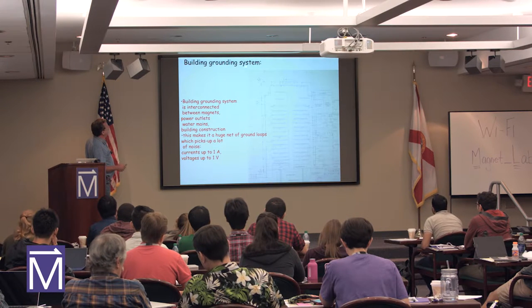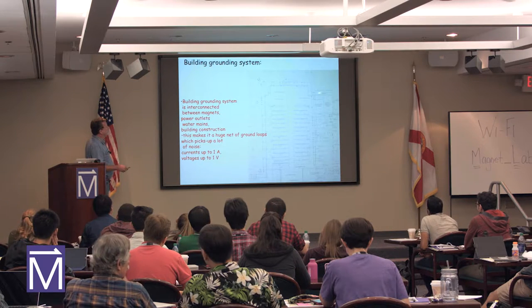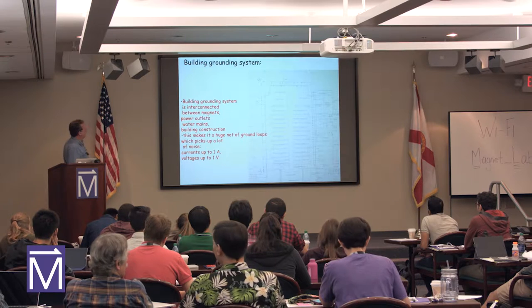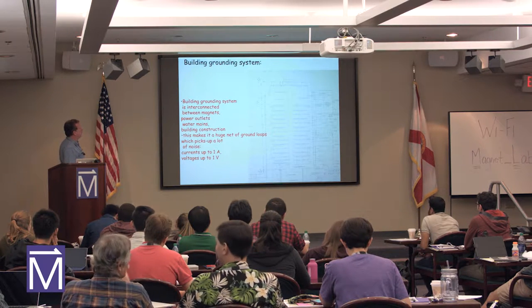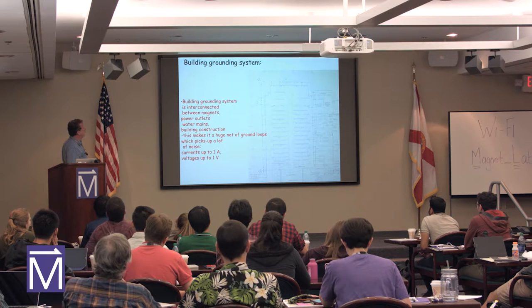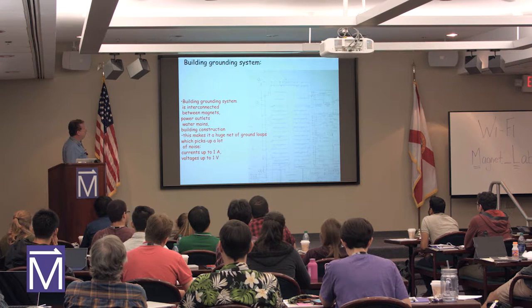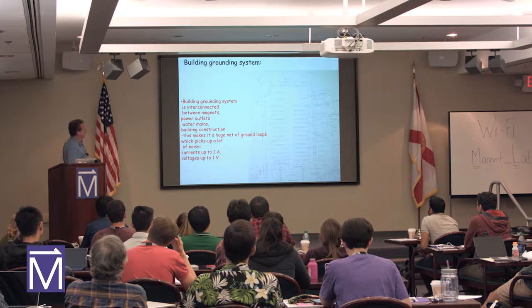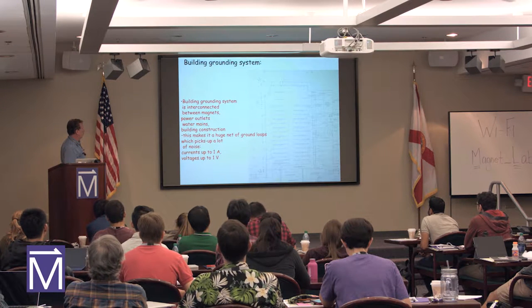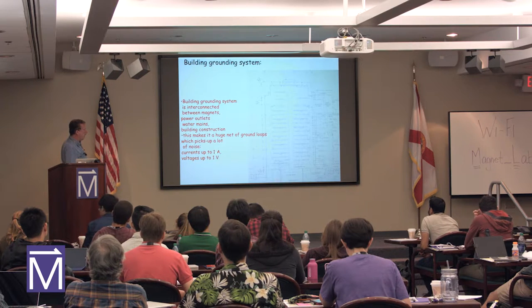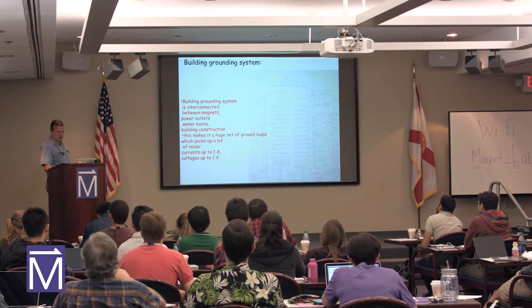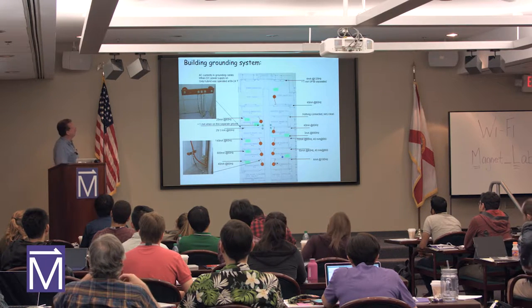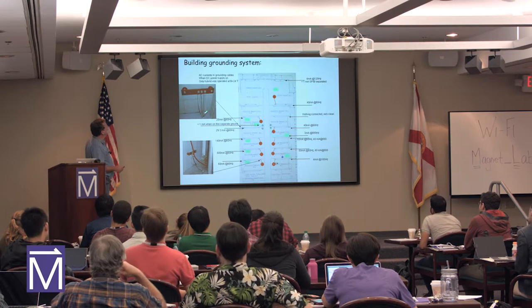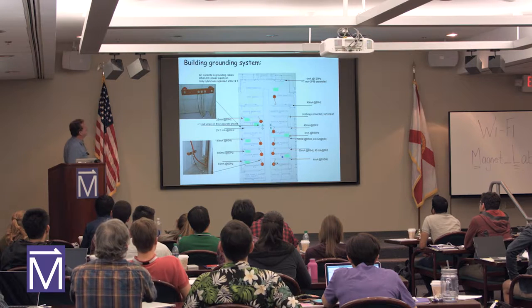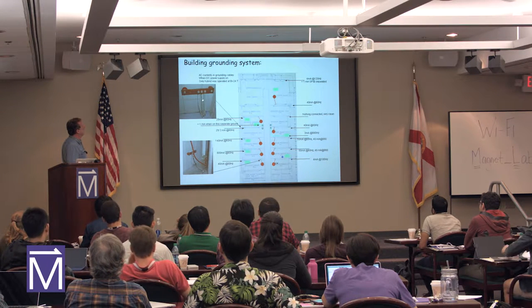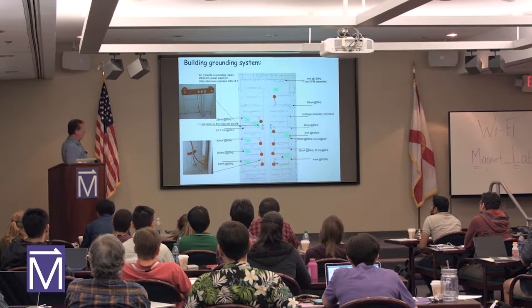Later, we built a new grounding system. This is a blueprint of all the magnets in the DC area. The building grounding system, and this is usually everywhere, is interconnected between magnets, power outlets, water mains, and building construction, and this makes a huge net of ground loops which pick up a lot of noise. And we observe here currents up to 1 amp and voltages up to 1 volt on this building grounding system. In the corner of each cell, you have this old grounding system. Usually, this comes from another cell, this comes from the magnet, and this goes to ground.